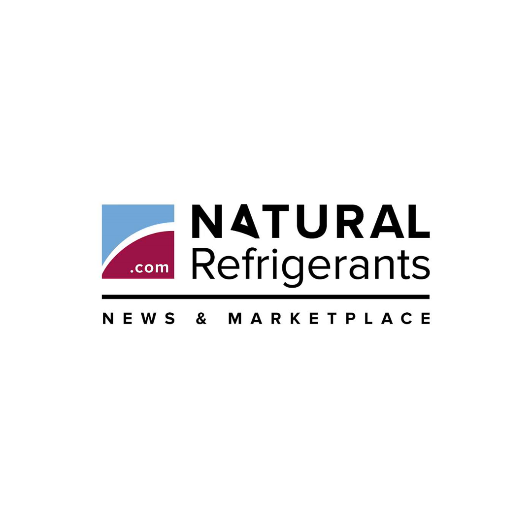Building on lessons learned from Polaris, Magnotherm developed its second-generation magnetocaloric cooler, Eclipse, which won the Innovation of the Year/Refrigeration Award at ATMO Europe 2025. It operates as an air-cooled chiller, providing a cooling capacity of up to 1 kilowatt, 0.3 tons of refrigeration. The company has produced 5 Eclipse units and plans to build 20 more in 2026.